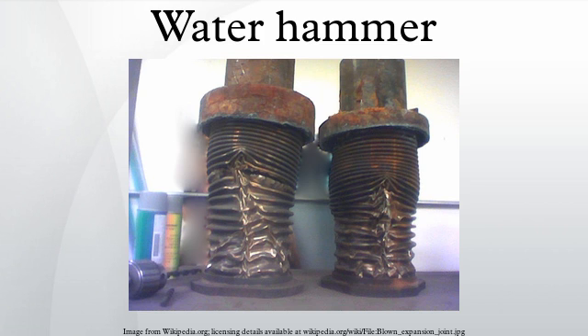For practical application, a safety factor of about 5 is recommended. Where P1 is the inlet pressure in psi, V is the flow velocity in feet per second, t is the valve closing time in seconds, and L is the upstream pipe length in feet.